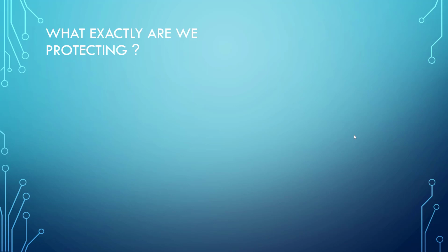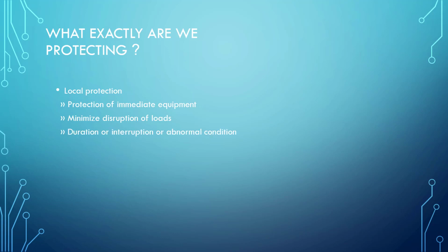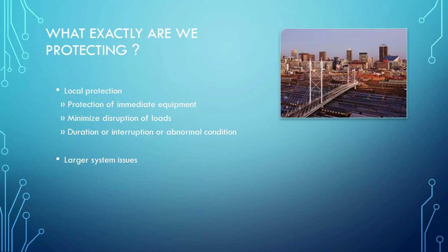We have a local protection, which is made of a protection of immediate equipment, such as your substation installations. Those will minimize the disruptions of loads if your system is well protected. Now you have also to look at the time it takes to recover from situations, so that you don't disrupt your load and create abnormal conditions in big cities. Now the larger system issues also, like a city like here is relying on a stable power supply, so you have to ensure that, because the impact on stability of larger system is very huge, usually resulting in economic cost.